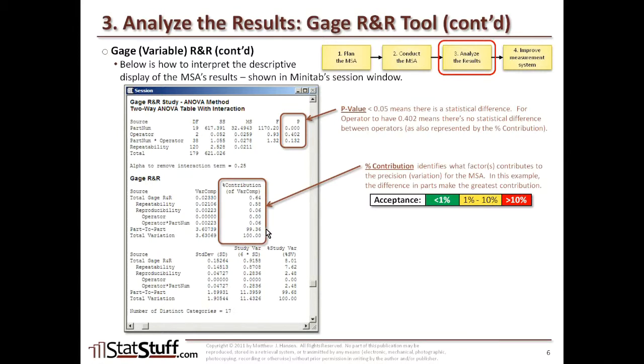In every instance here, when looking at the total gauge R&R, repeatability, and reproducibility — whether broken down by operator or operator and part number — all values are less than 1%. But most of the variation is in part-to-part, which we already know because different parts were actually supplied to these different operators.